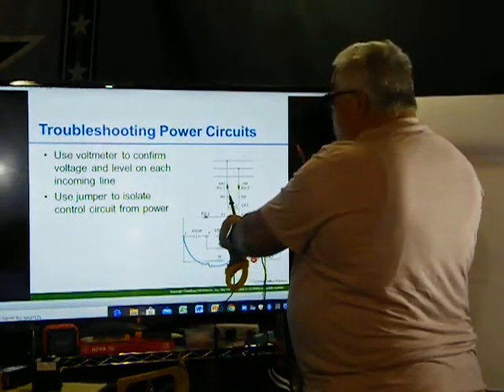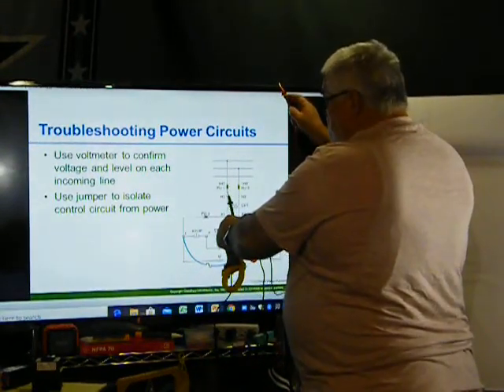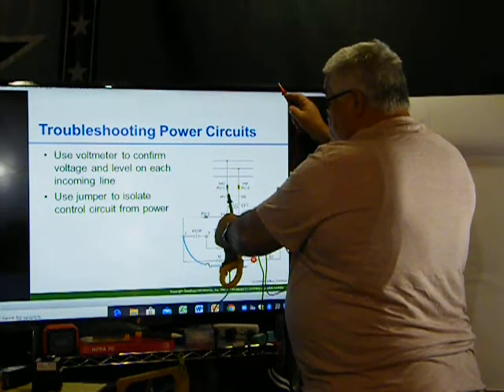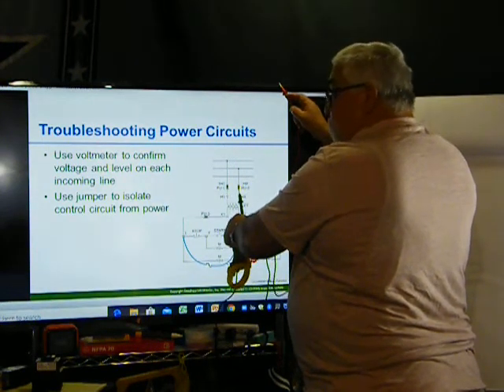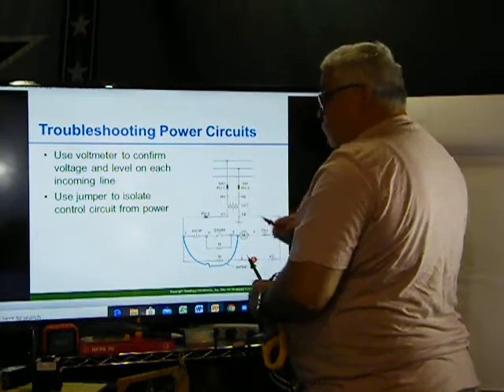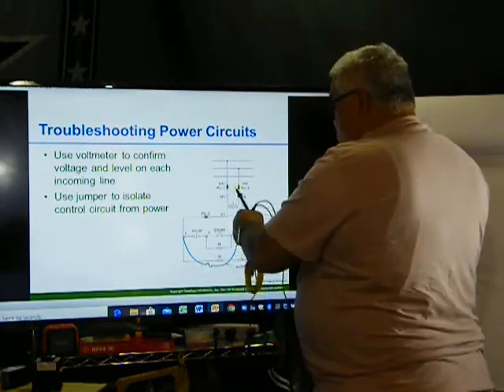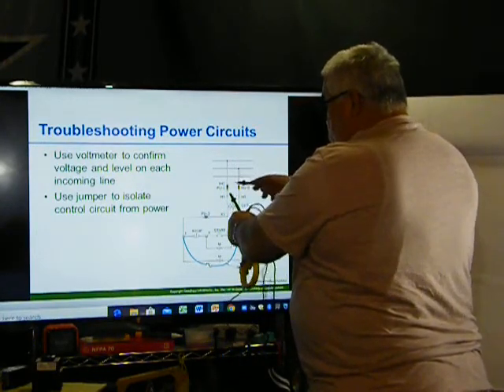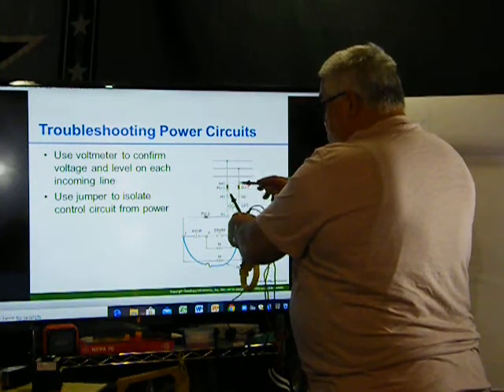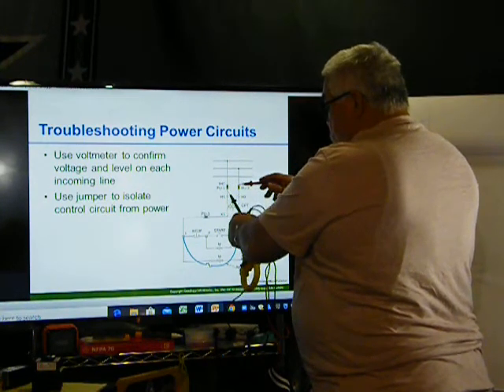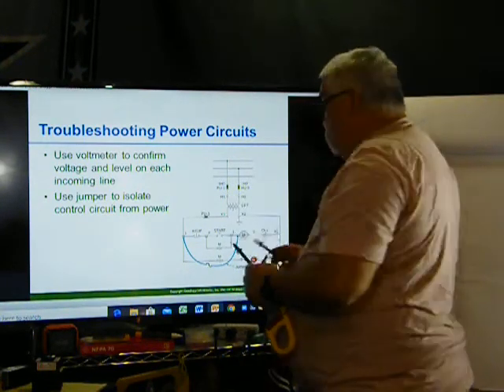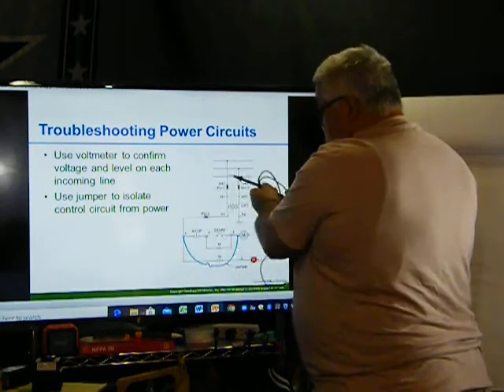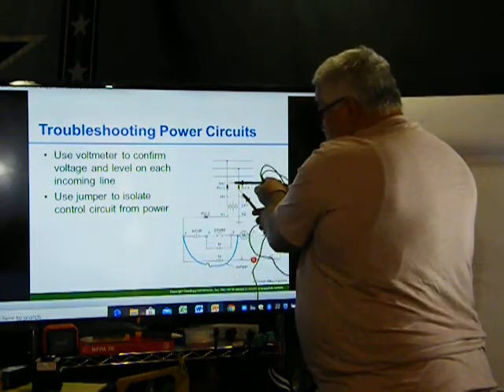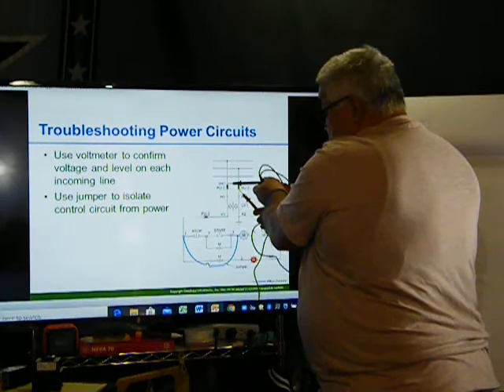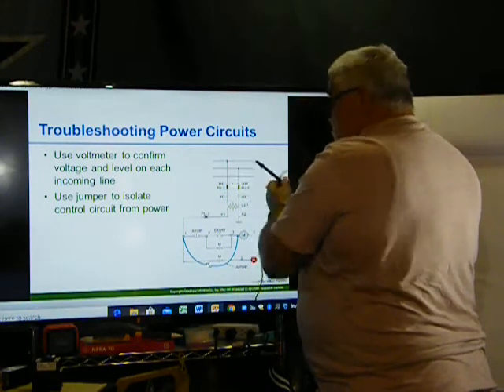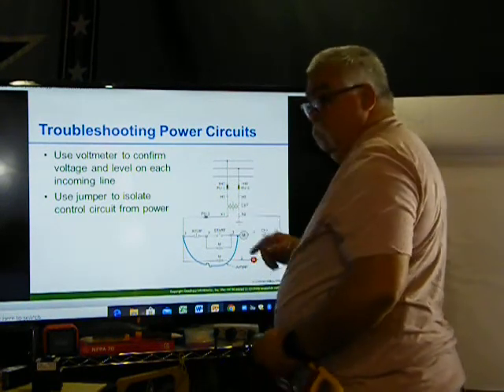Okay, now I can go from here to the ground. I got 240, I got 0. That tells me this fuse is bad. How else can I check? I can go from here to the top, from here to the top here. That should give me 480. I should go from here to the bottom of the fuse. It should give me 480, but it's not giving me anything. Again, now I found out this fuse is not working.